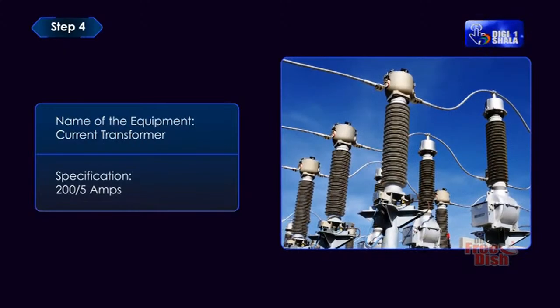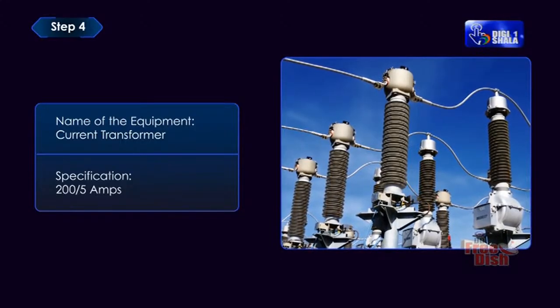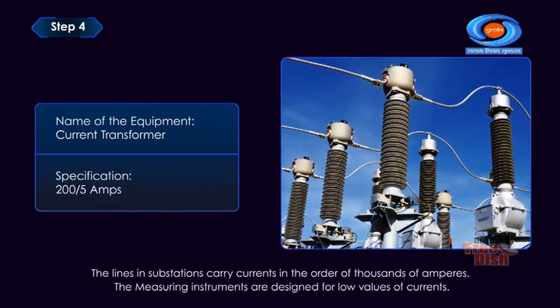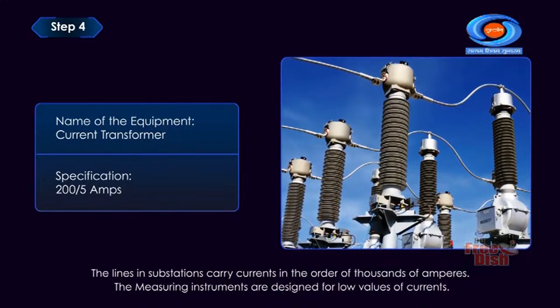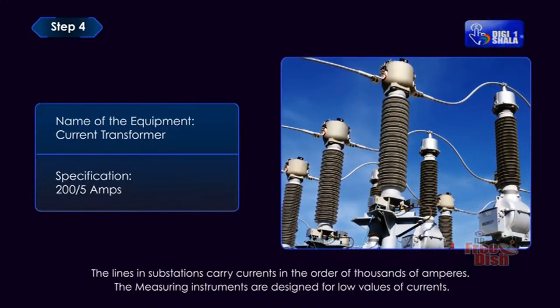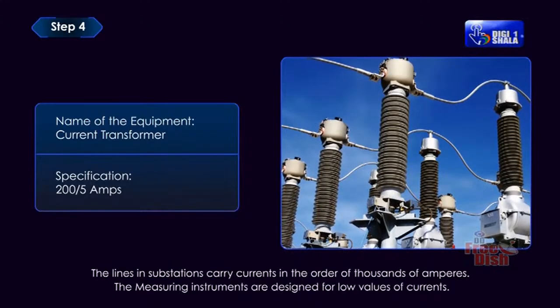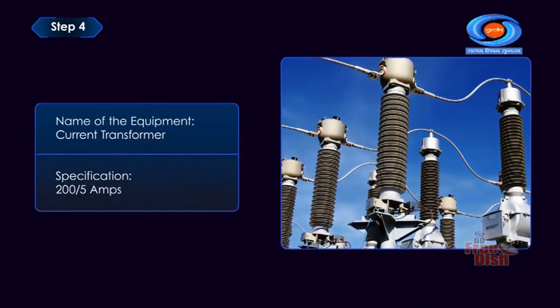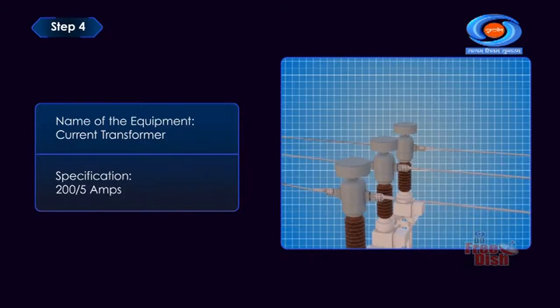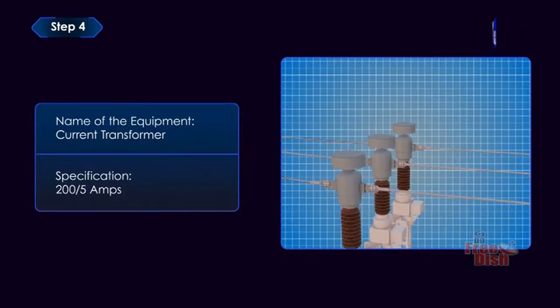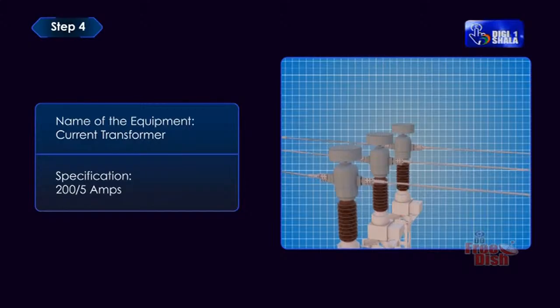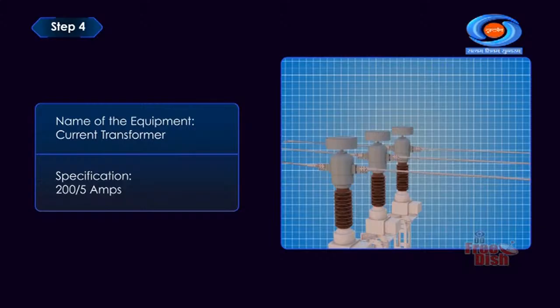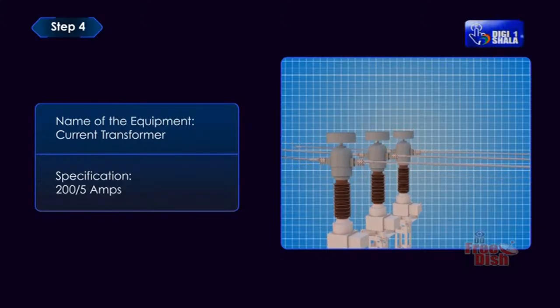Current transformer: 200/5 ampere. The lines in substations carry currents in the order of thousands of amperes. The measuring instruments are designed for low values of currents. Current transformers are connected to lines to supply measuring instruments and protective relays. For example, if a 100/1 ampere CT is connected to a line carrying 100 ampere, then the secondary current of the CT is 1 ampere.